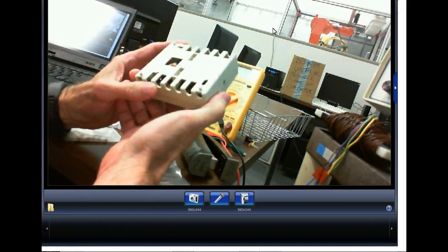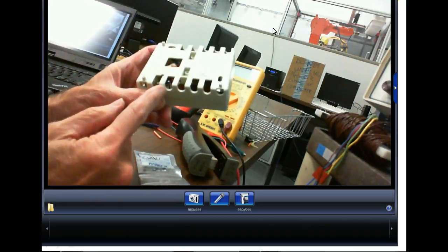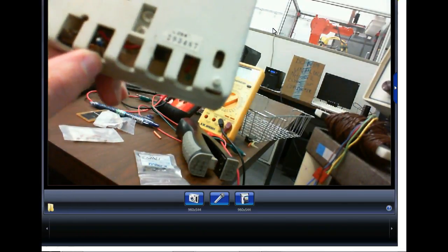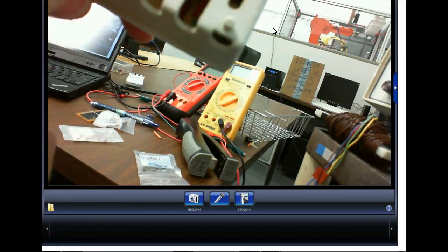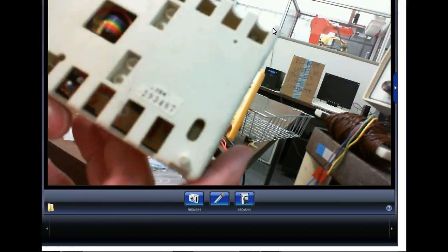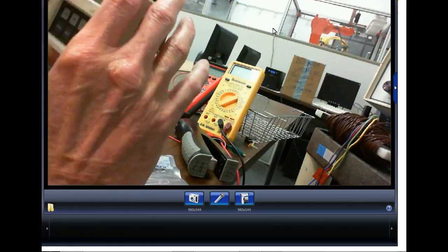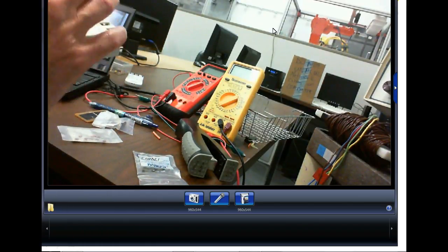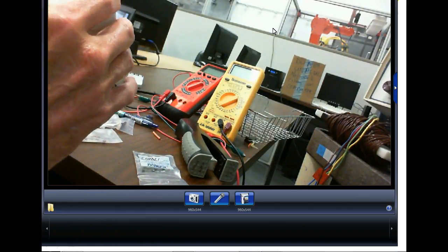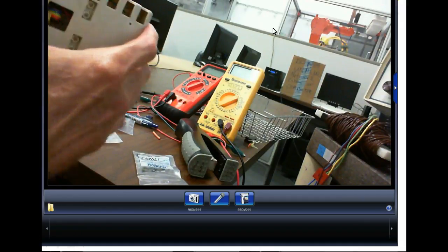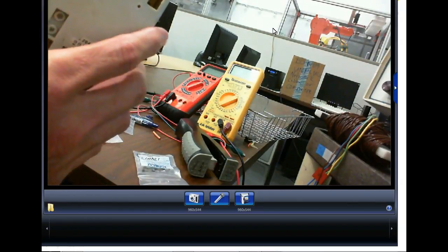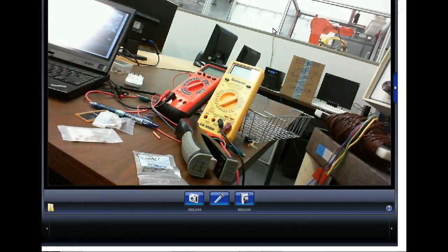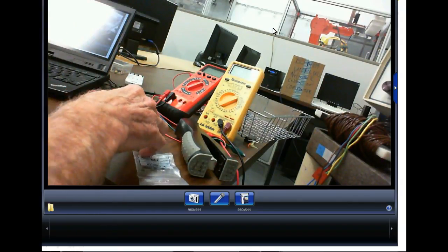And then I look at the back, and right here, see the little white dot right there? You know what that is? That's the thermistor. So this guy right here is using a thermistor, and I like this one because you can see the dang thing. Most of the time you'll see vents on the back of your digital thermostat, and there'll be a thermistor mounted up in there. So these guys are used all over the place.